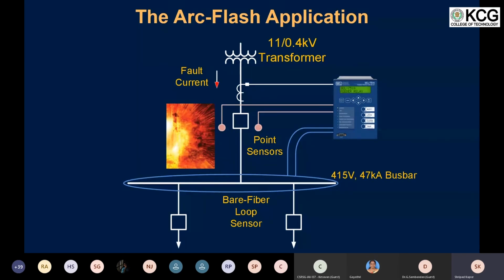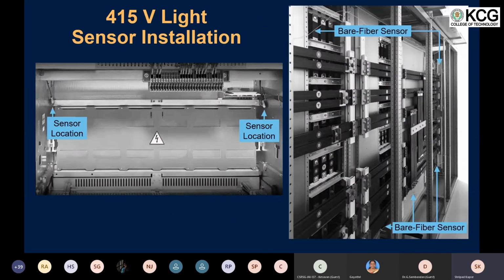So in this particular installation, we had installed two point sensors in the breaker chamber, and a bare fiber sensor running through the bus bars of the 415 volt switchboard. Sorry, 415 volt switchboard. So these are some of the installation pictures. You can see the point sensor being mounted in the breaker chamber, and the bare fiber sensor being mounted on the LV bus bar arrangements.